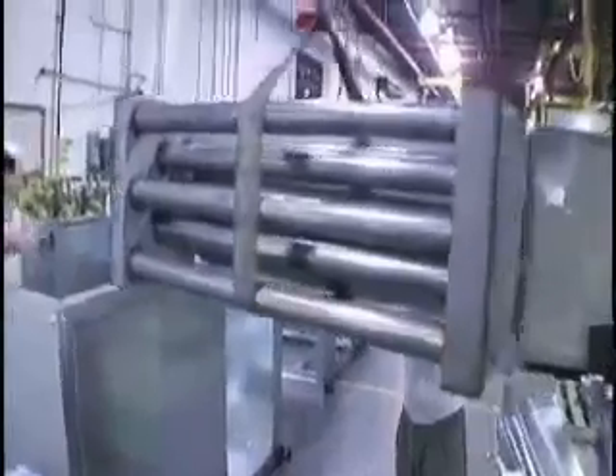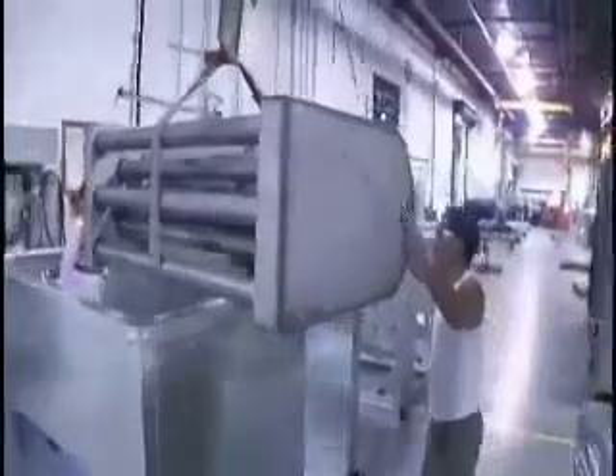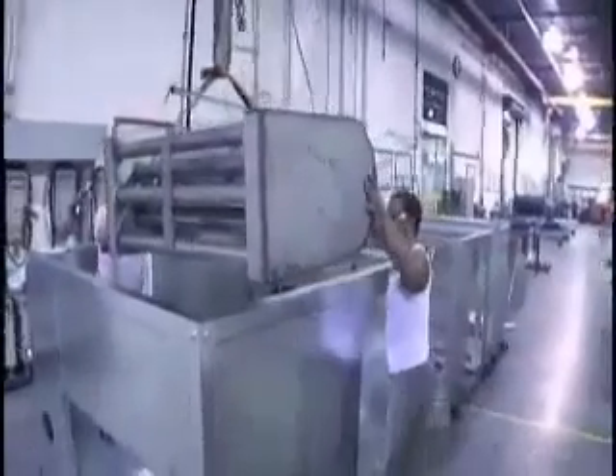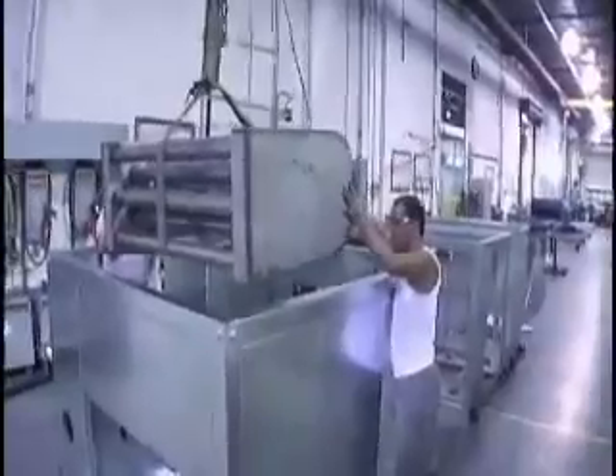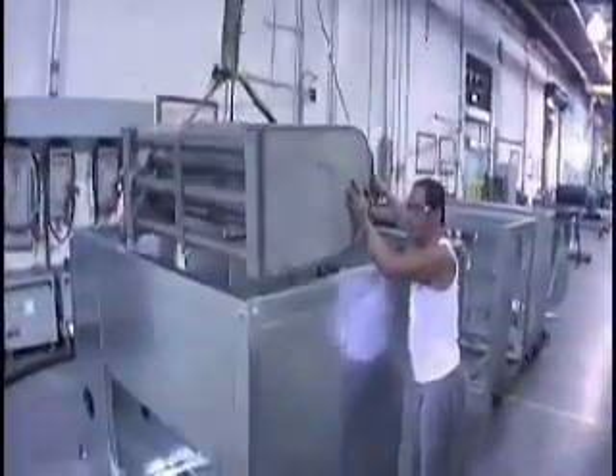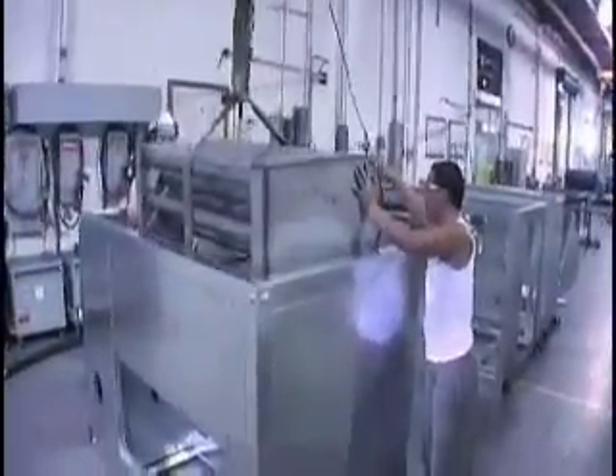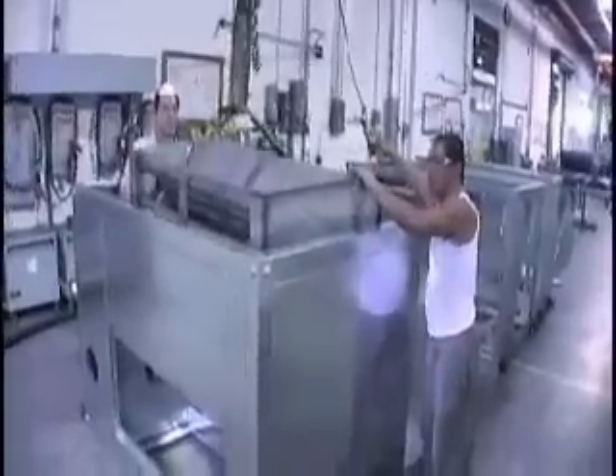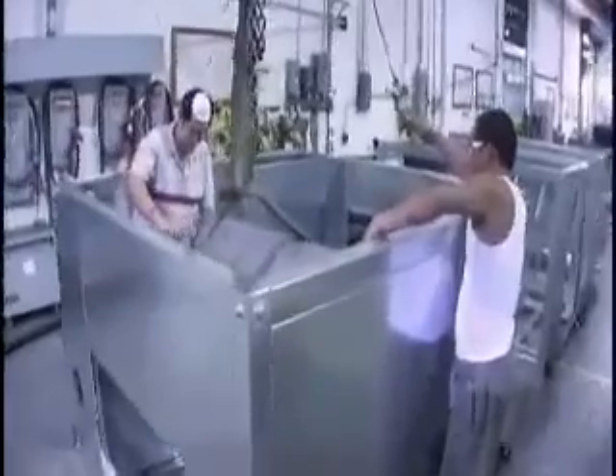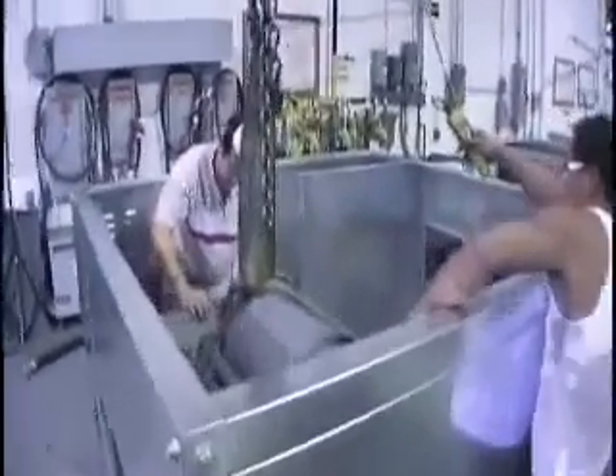So we have a unit that at its very essence has the ability to handle 4 levels of filtration, an 8-row coil, a 2-row reheat coil, plus a very high efficiency gas-fired burner. We were looking for this very high turndown opportunity. If you were to just go by the standards, you could set your unit up for high fire, you could set your unit up for low fire, and as long as you're clean at those 2 points, they allow you to claim that as your turndown.